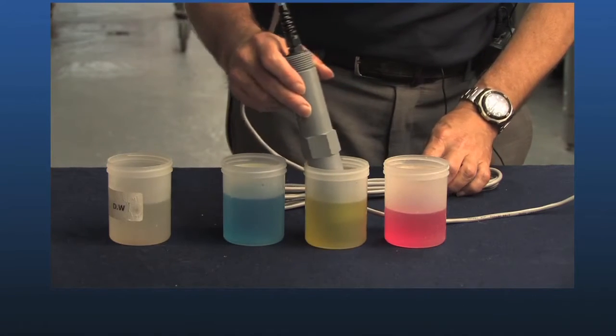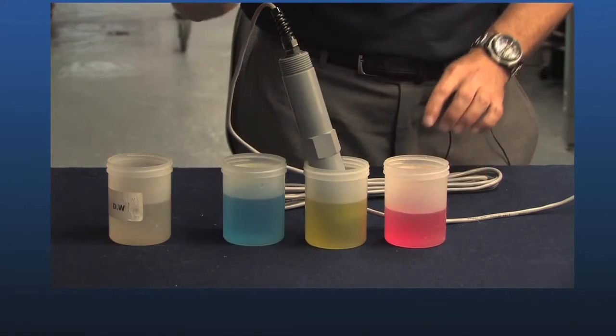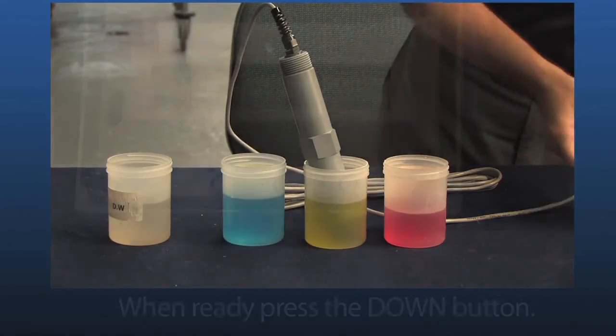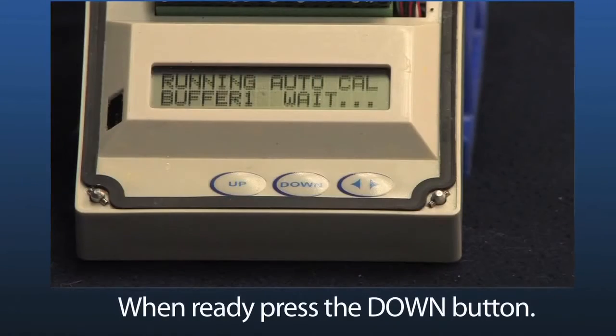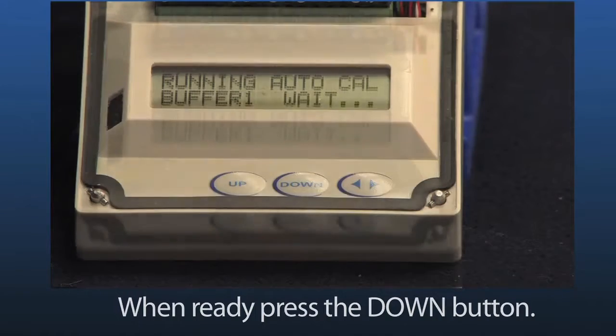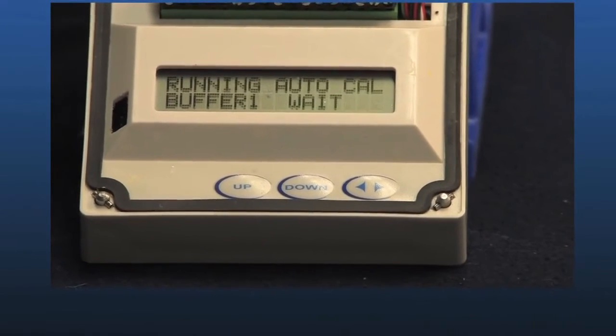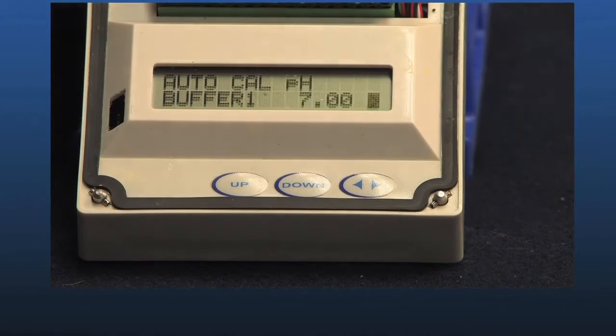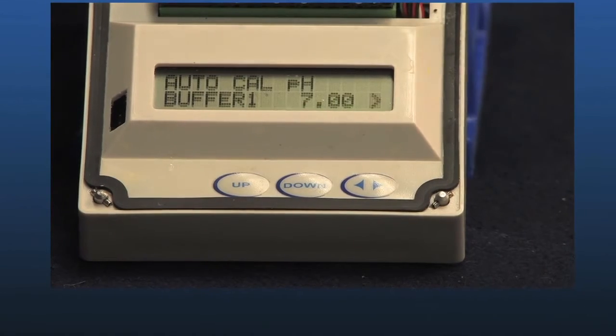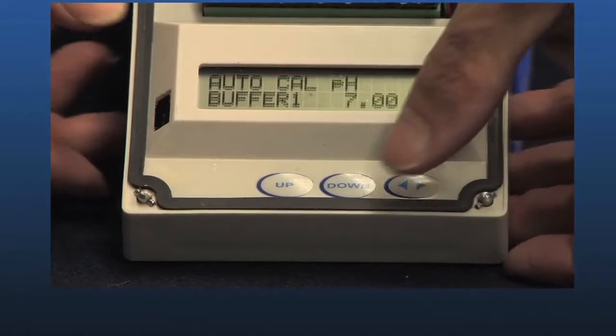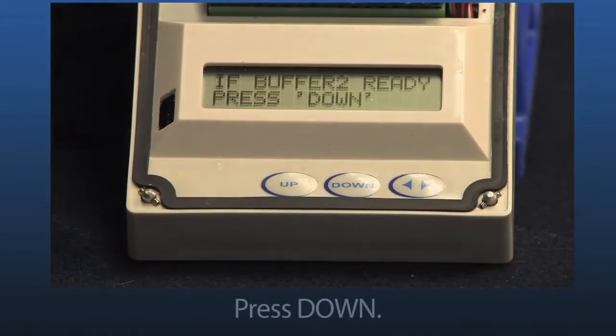I wait at least 30 seconds. 2 minutes is even better. And when I'm ready, I press down. Now it's thinking. It's measuring the output of the probe. And when it's done thinking, it realizes that the probe is in pH 7 buffer solution, which is correct. So now I'm going to press down again, and it says if buffer 2 is ready, press down.